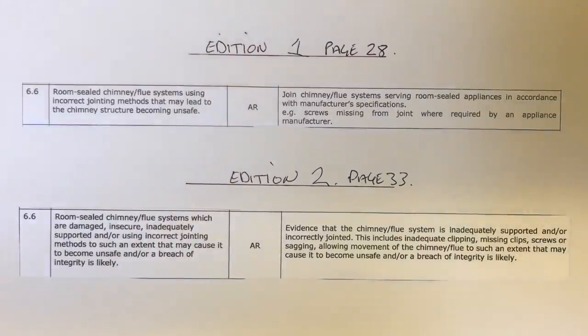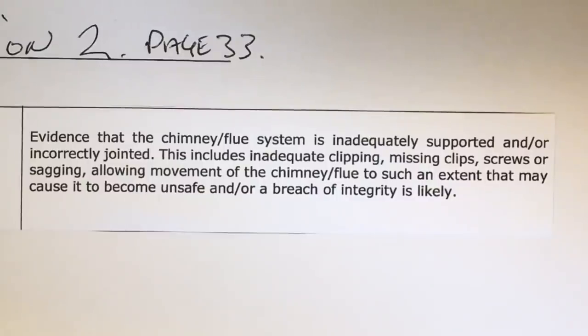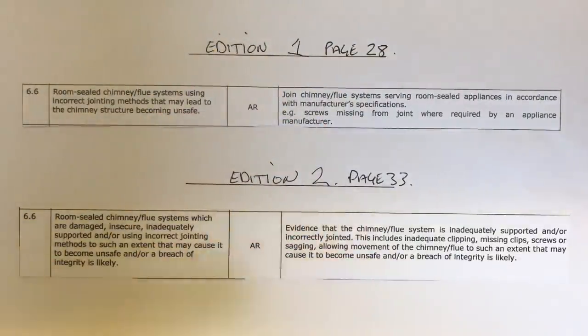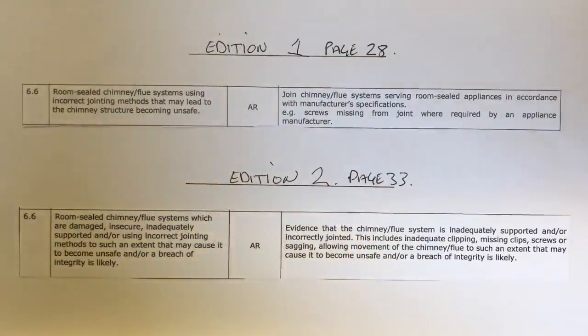Table reference 6.6 has been revised to provide guidance for room-sealed chimney flue systems which are damaged, insecure, inadequately supported, or using incorrect jointing methods to such an extent that it may cause them to become unsafe and/or breach of integrity is likely. It's basically a rewording with a few additional details to help when classifying flues — such as flues going through lofts without any support, which would be classified 'at risk', and if products of combustion are entering the loft it would be classified 'ID'.